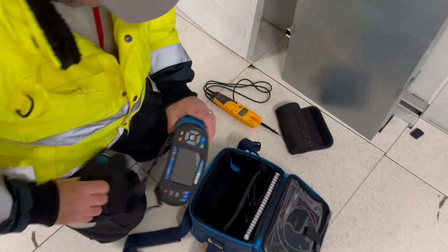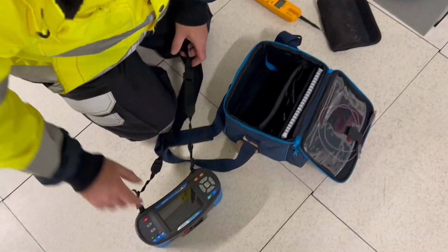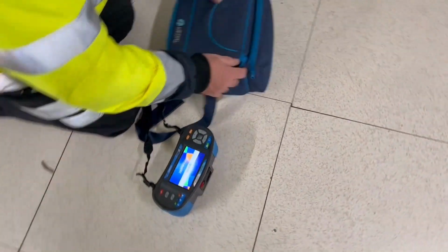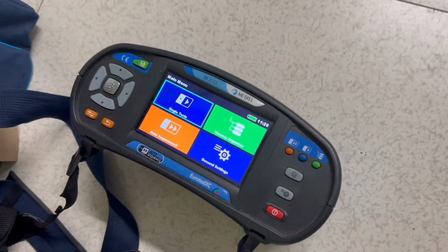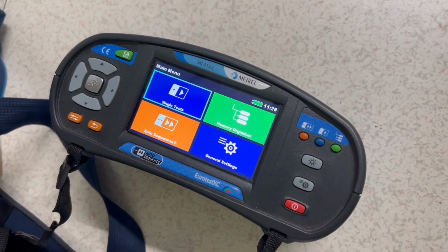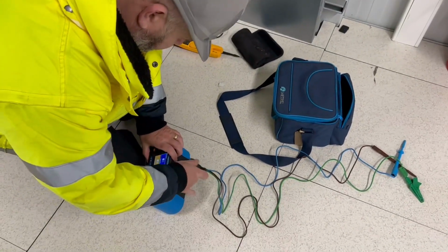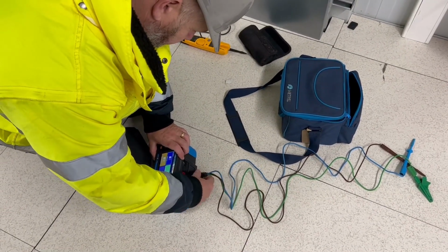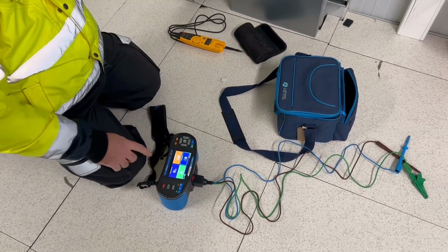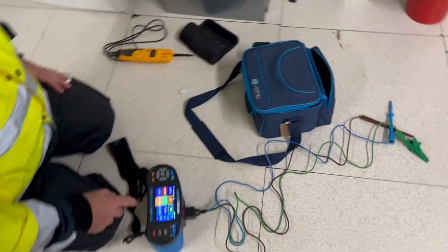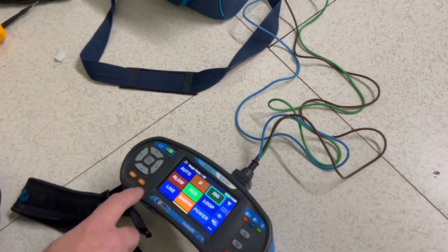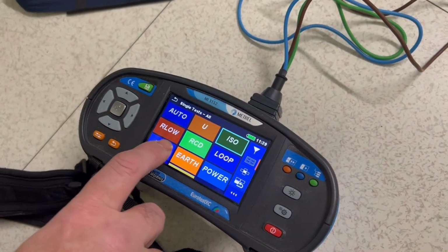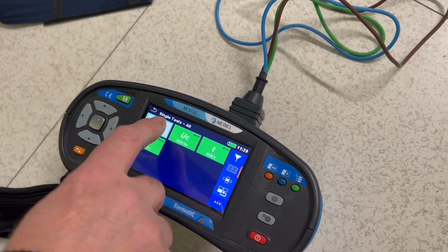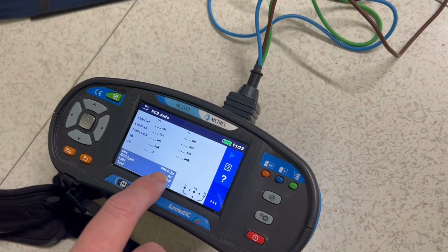Okay, our instrument of choice for this is this Metrel multifunction tester. One of the options it has under the single tests is an auto sequence which executes 8 tests. The connection for this is 3 wire, so we'll be using one single phase connection, one neutral connection and the earth connection. We select RCD and auto function.